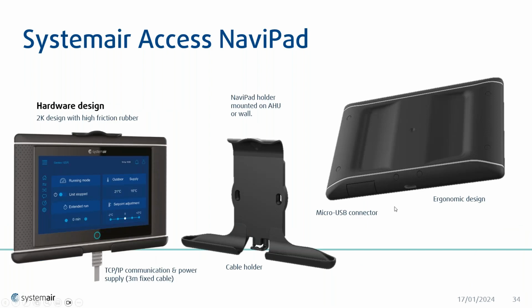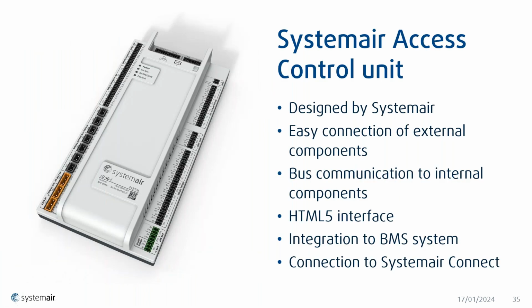You have your ergonomic design, Micro USB connector, and then the actual heart of the unit itself, which is designed by SystemAir. We have easy connection to your external components. As I mentioned, it is an internal bus communication to the components so that you have that two-way communication. However, BACnet and all the additional protocols which you need in order to communicate to your BMS systems are available. The actual bus communication is just internal to the unit, but BACnet, etc., and all the other protocols that you need are supported by the actual program itself.